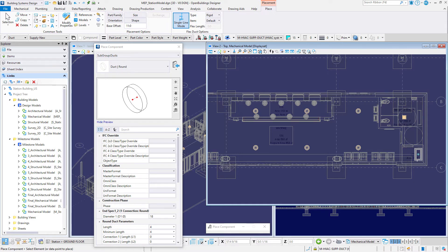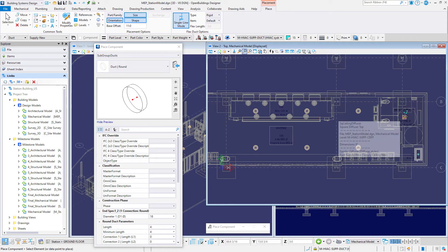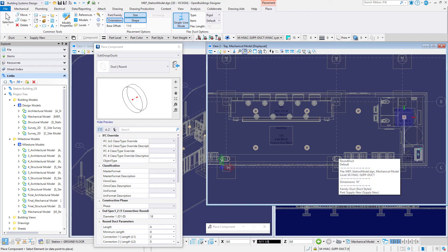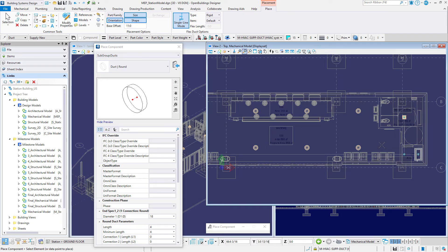Next, we will connect the diffusers to the main duct route. With the round duct still selected, turn on the orientation, size, and shape on the placement ribbon — these will be determined from the diffuser when selected. Snap to the diffuser in the women's toilet room and data point to accept. Select the main duct route, and a single-line route is drawn from the diffuser to the main duct, finding the shortest path.